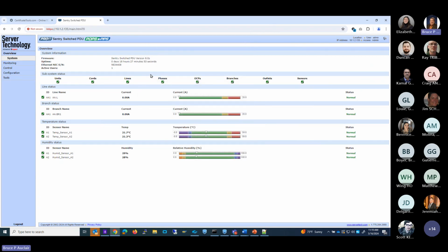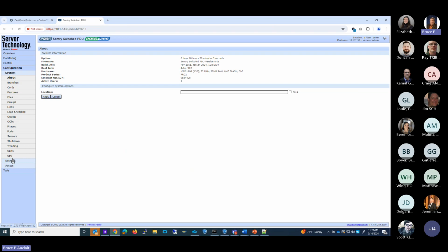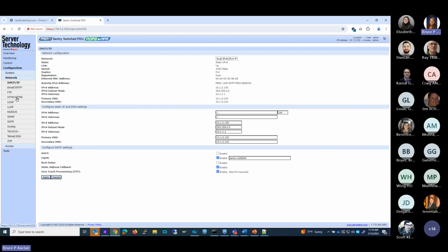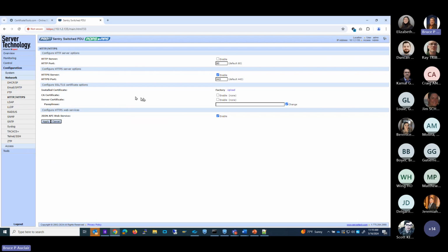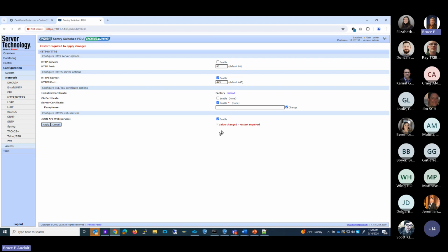All right, let's take a look at what is needed to install a trusted certificate. And that's going to be to go to the configuration option, then network, and then the HTTPS page. As mentioned previously, it's multiple steps. Step number 1 is to enable the option that allows you to install your own trusted certificate, which is clicking the enable box. You need to then click apply. It will give you a message that restart is required. It is not actually required at this point. It will be required after we install the certificate files, the key file and the CRT file. So that was step number 1, to enable the option.